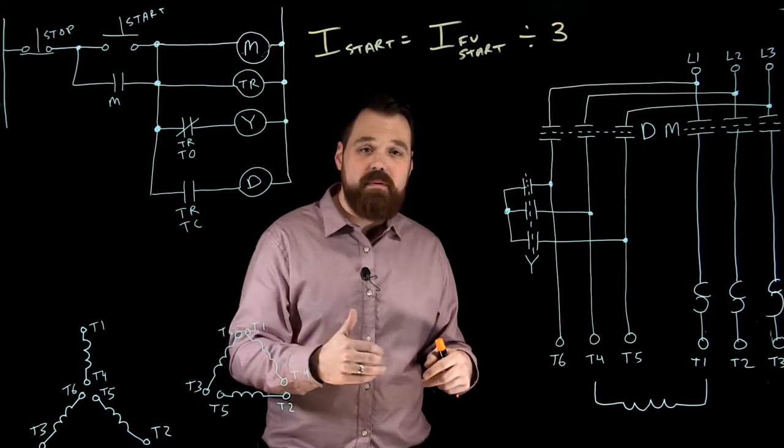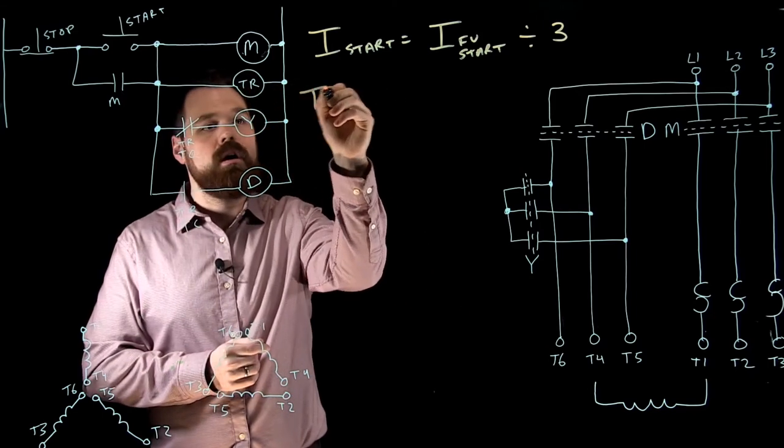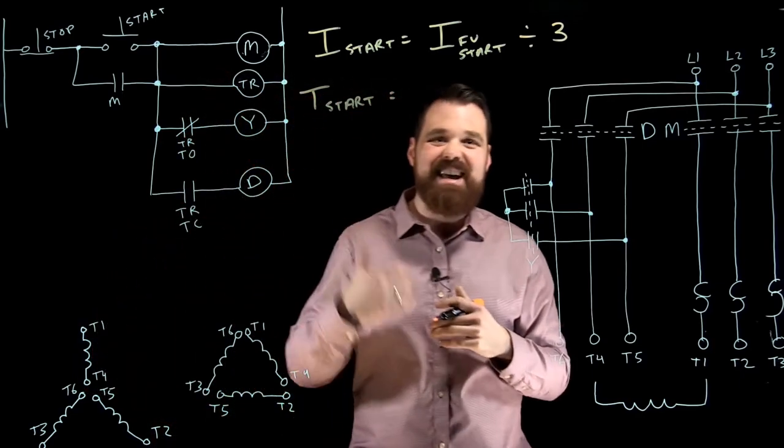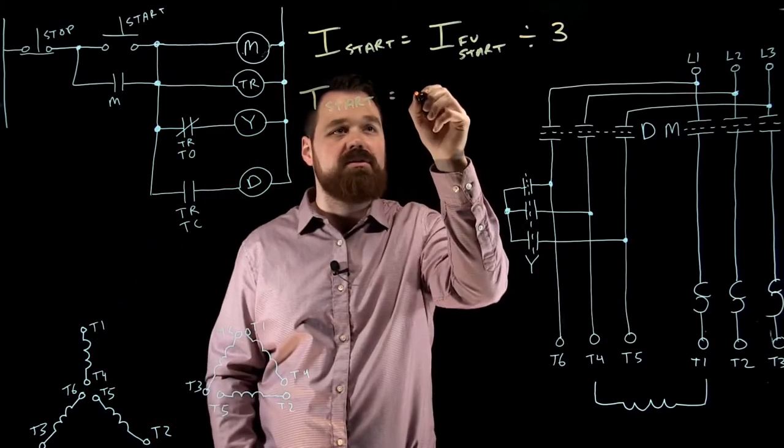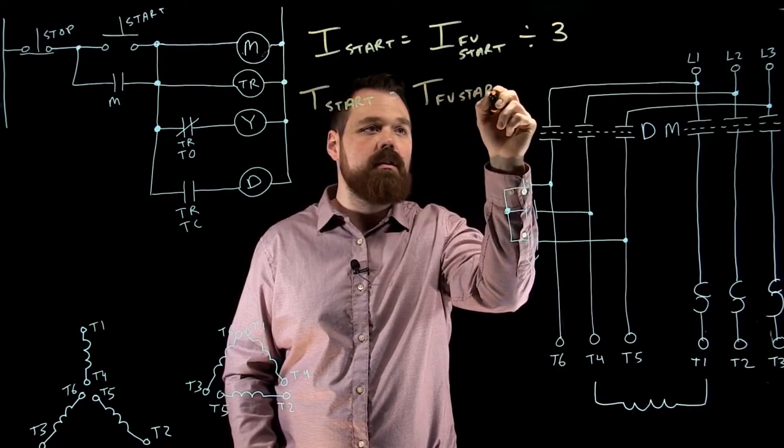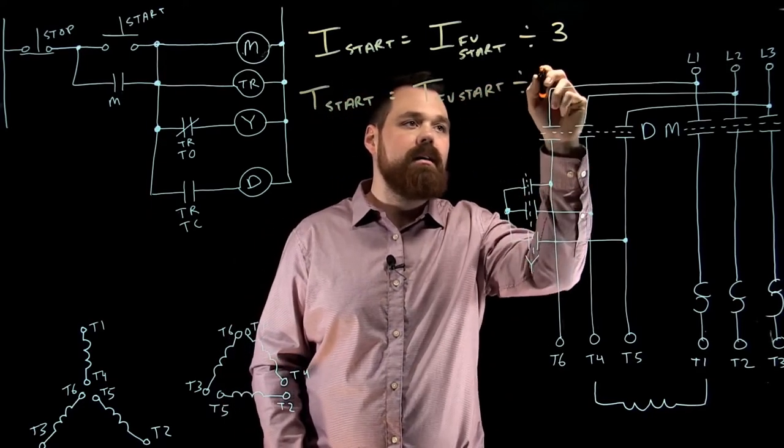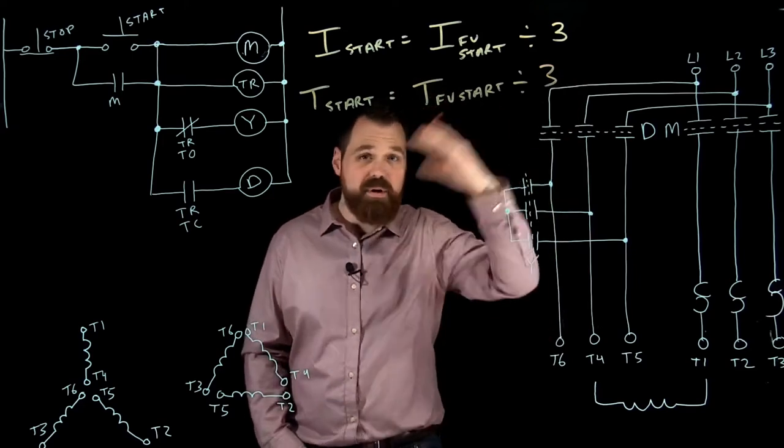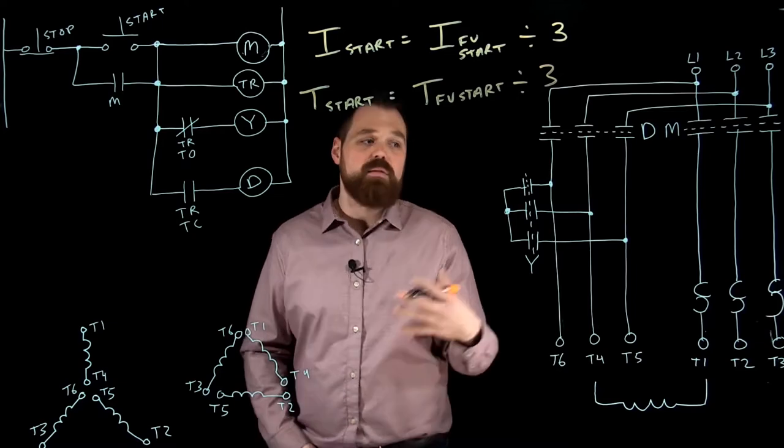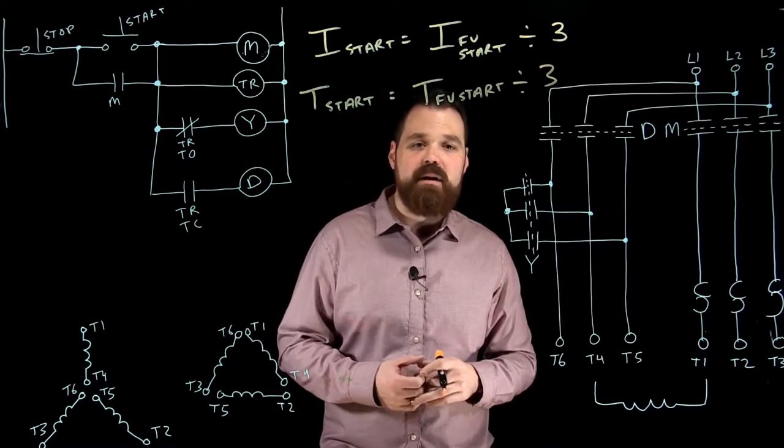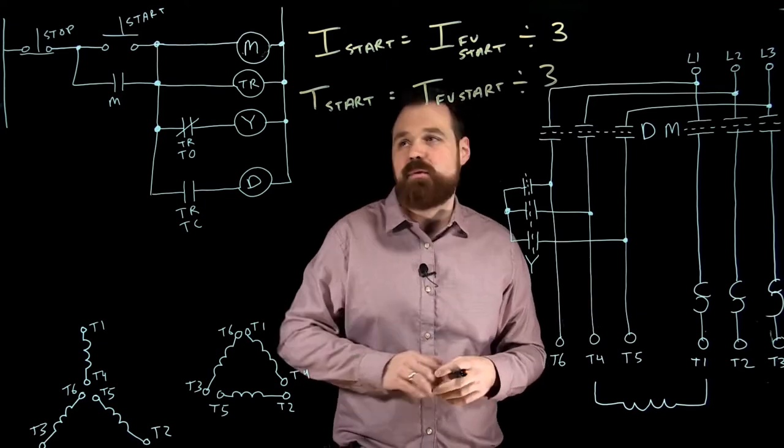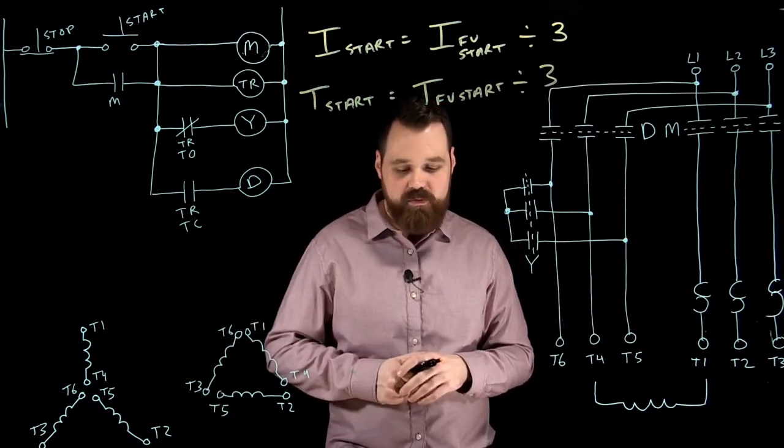Unfortunately, with that huge drop of inrush current, our torque at start sees that exact same relationship, so it's also going to be our torque of our full voltage start divided by 3. So we see a big drop in current, big drop in torque, but we can maybe start that motor with smaller conductors. This again is a motor where you'd want to start it and then start adding load on afterwards once it's switched over into that delta formation.